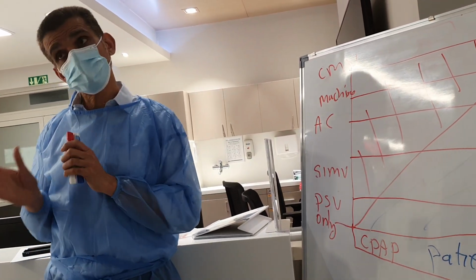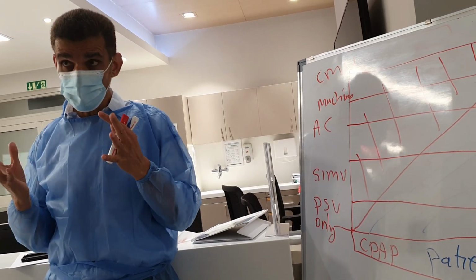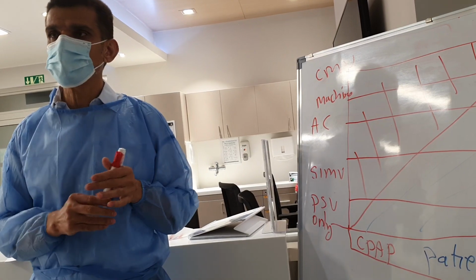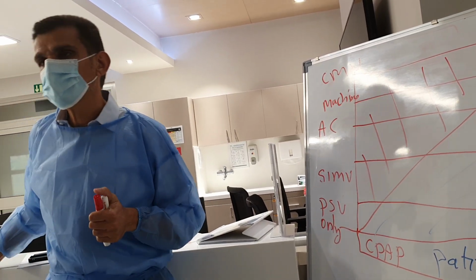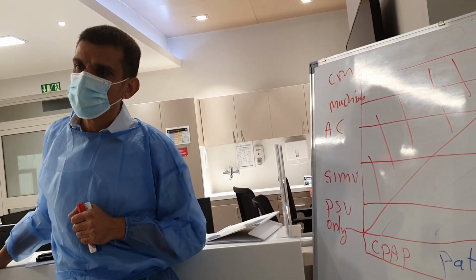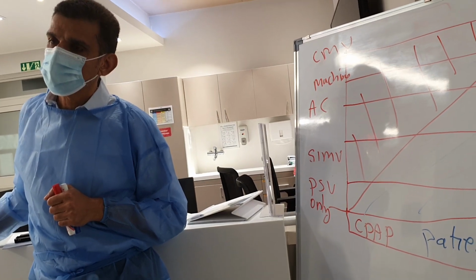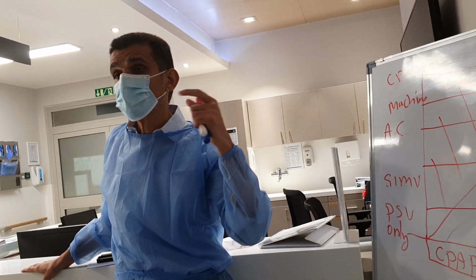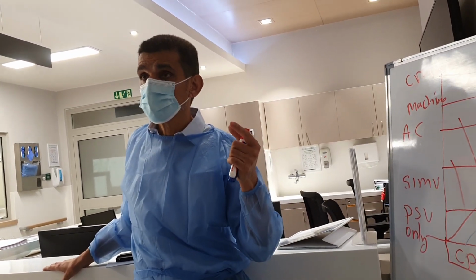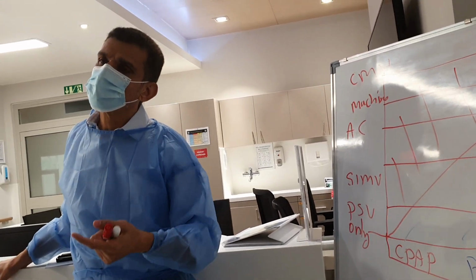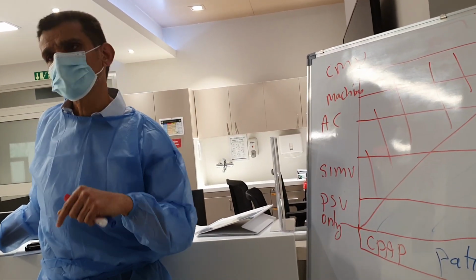Okay, and we have two strategies in ventilation. We have the volume and the pressure. I have to show you the internal structure of the ventilator to understand the difference. Basically volume is used for short ventilation, for big-size adults and children, such as a 1-hour, 2-hour, or 3-hour surgery. If you need more than 24 hours, even in an adult, it's better to use pressure.